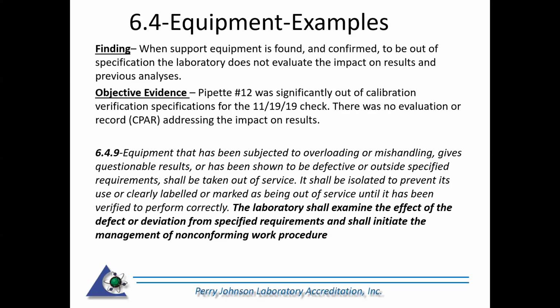It says the laboratory shall examine the effect of the defect or deviation from specified requirements and shall initiate the management of nonconforming work. So this pipette was significantly out of calibration. The laboratory didn't do anything in regards to looking at how that impacted their test results.